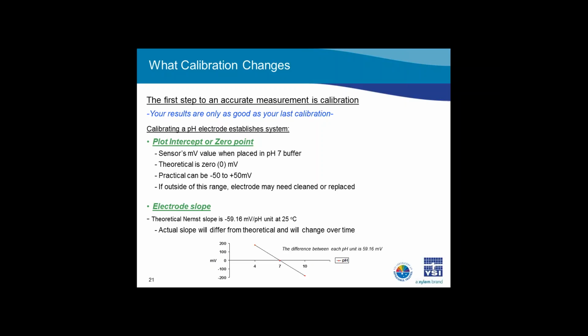On the other hand, it's important to remember that many instruments in use today are of the older analog type. In this case, it is very important that you calibrate the sensor and meter as a system and keep them together, since the calibration is stored in the meter in this instance. In the end, regardless if you are using an analog or digital system, your data is only as good as your calibration, so be sure to take the time to do a proper calibration.